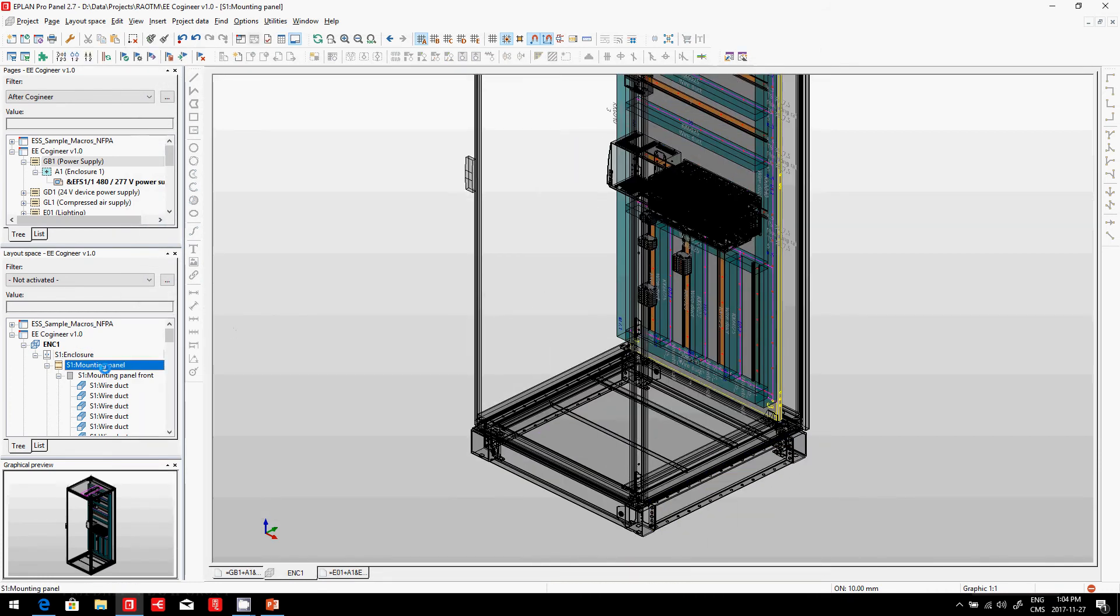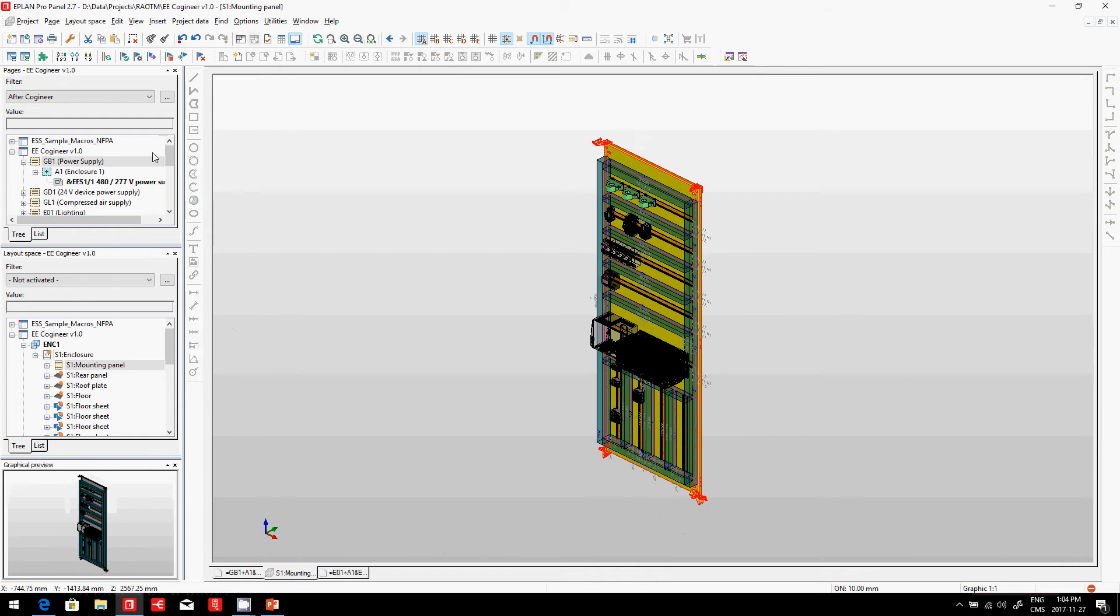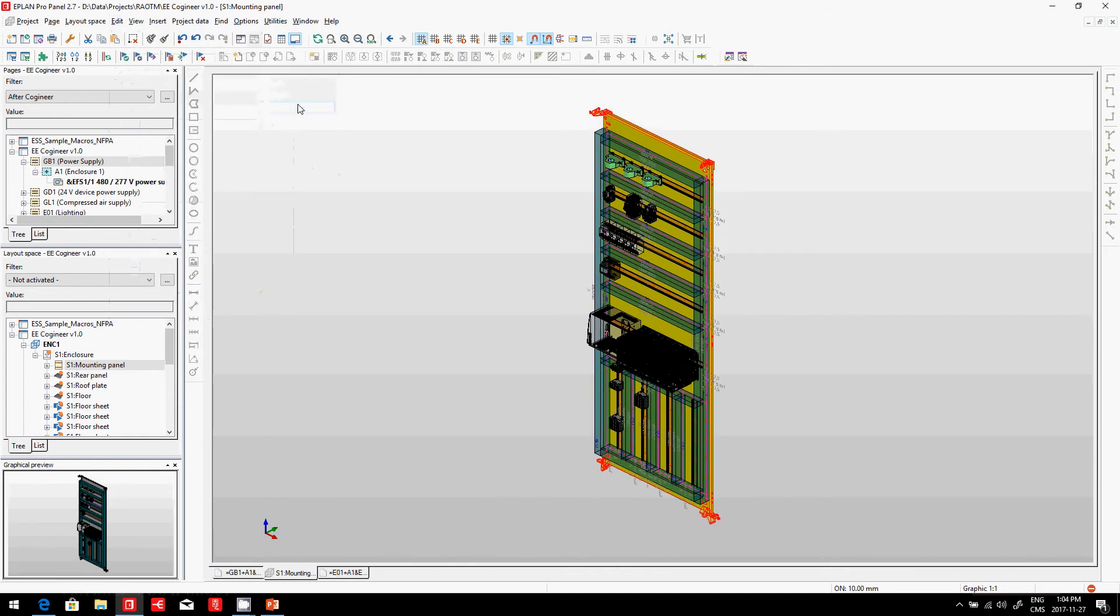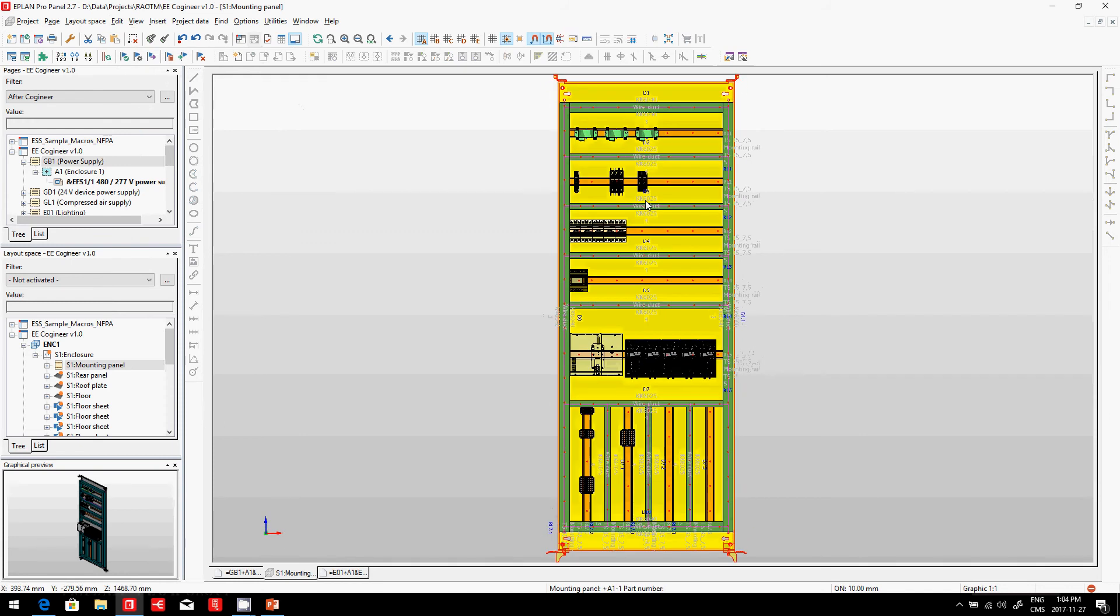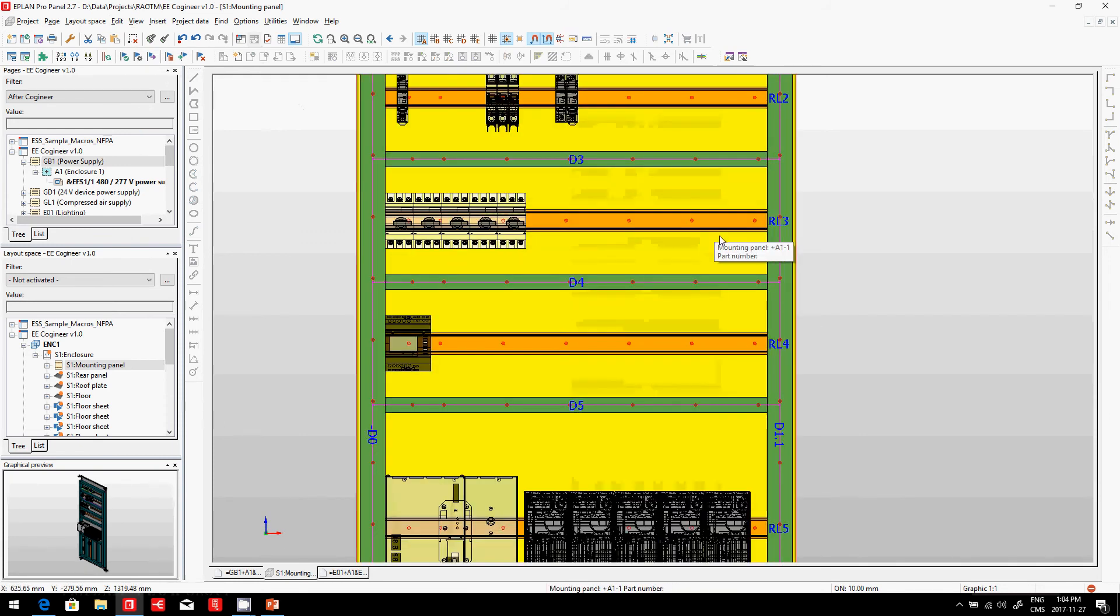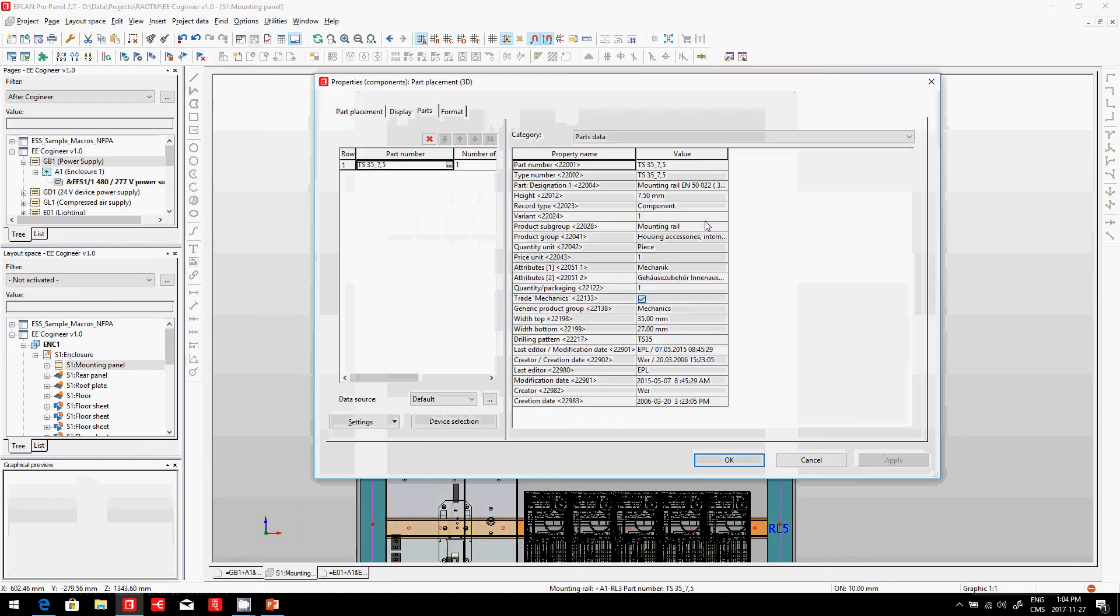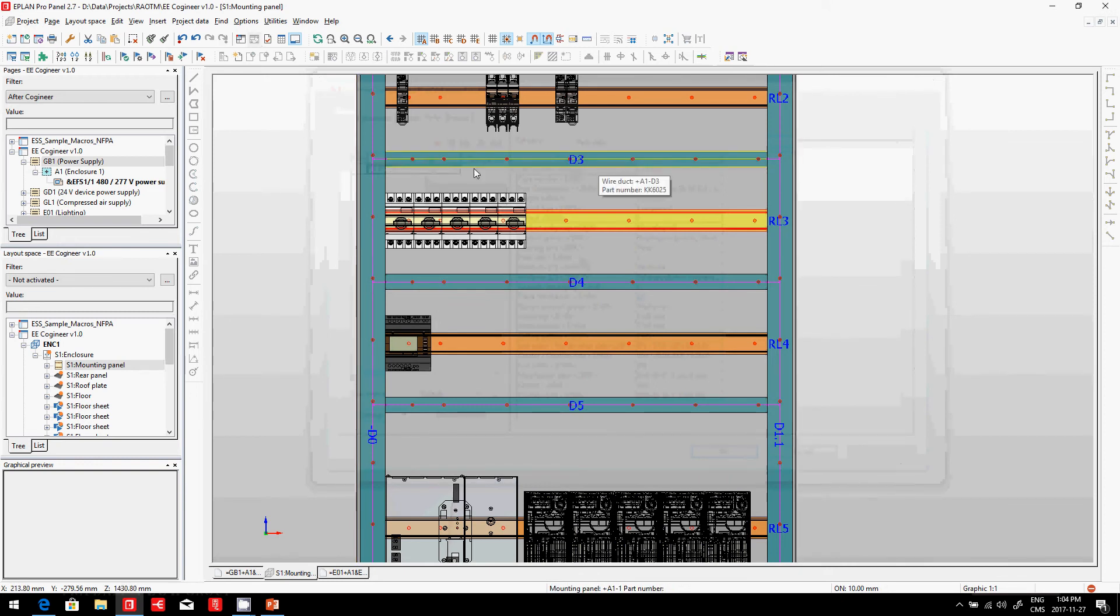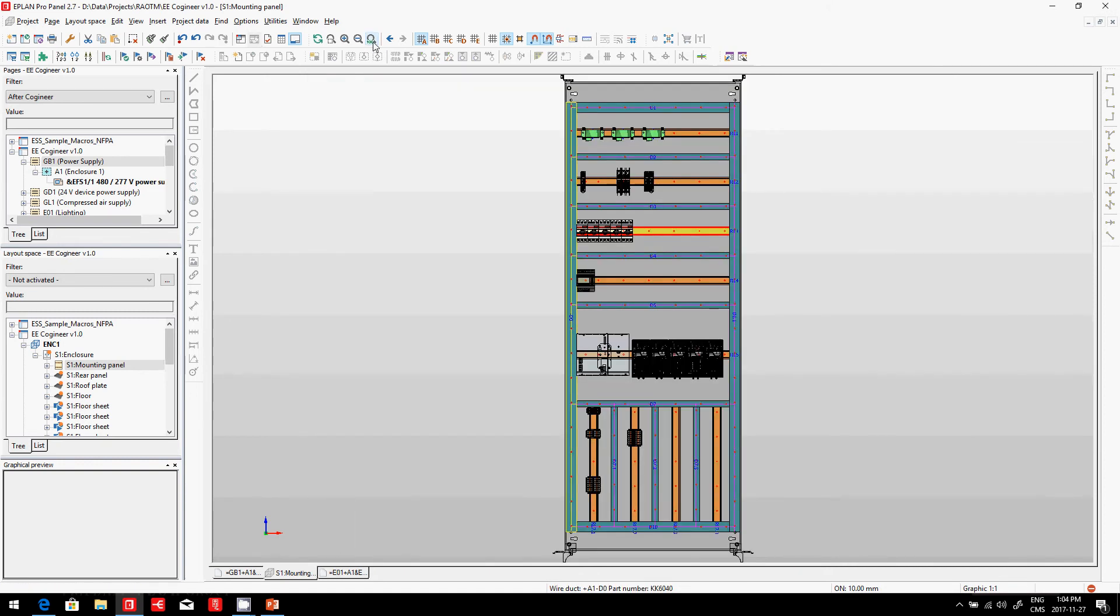But, far more interesting is actually how we built it. We actually went and constructed here our backplate. And, as we built the backplate, you can see here, if I zoom in, we can see all the different holes that are directly punched in based on the material that I picked. So, here is a certain DIN rail or a wire duct. And, this sums up to quite a lot of small holes I have to do.